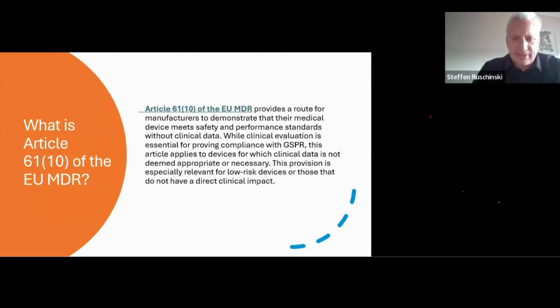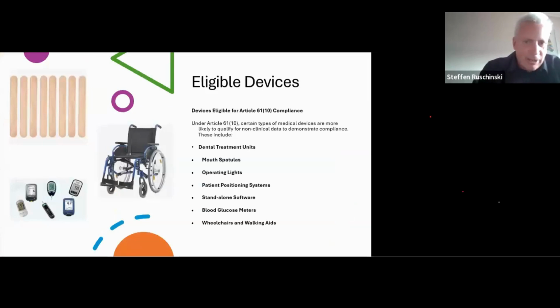It should be applied to lower risk devices where the performance can be sufficiently demonstrated through non-clinical data like mechanical testing, performance evaluations, or other bench testing. What are devices that normally can be eligible for this? Under Article 61(10), certain types of medical devices are more likely to qualify for non-clinical data to demonstrate compliance. These include dental treatment units, mouth spatulas, operating lights, patient positioning systems, standalone software, blood glucose meters, wheelchairs, and walking aids. These devices typically do not require direct clinical evaluation and may not provide clinical benefits, making clinical data unnecessary. Instead, performance and safety can be proven through non-clinical means.